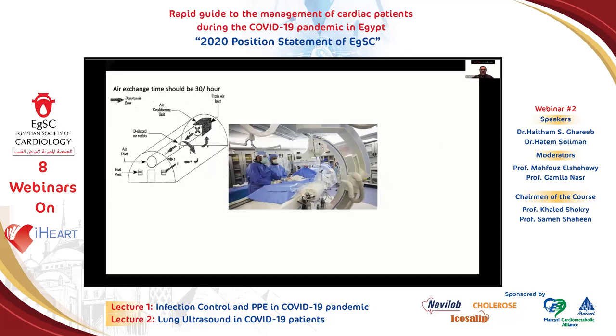Another important point inside the cath lab is to control the airflow. The majority of cath labs worldwide do not have a negative suction or negative pressure system. In exchange, we must know from the medical bioengineering team the air exchange time inside the cath lab, which is the time the air spends from the source till the exit or air duct. This air exchange time should be 30 times per hour, and the minimum is 15 times per hour.